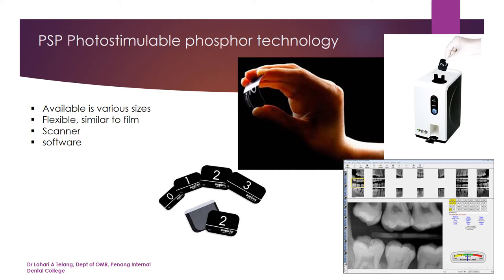The advantage of PSP is that it's more flexible and very thin, similar to film, so it fits well into the contours of the oral cavity. It comes with a scanner — after the PSP imaging plate is exposed to x-ray radiation, you take off the barrier envelope, and the sensor goes through a laser scanner. The sensor comes out, can be reused, and you get the image within 10 seconds on your screen.